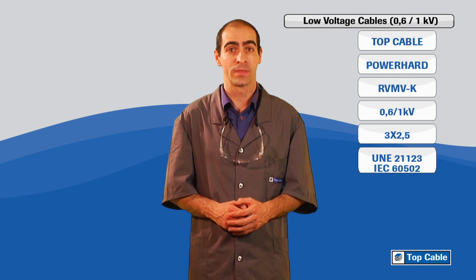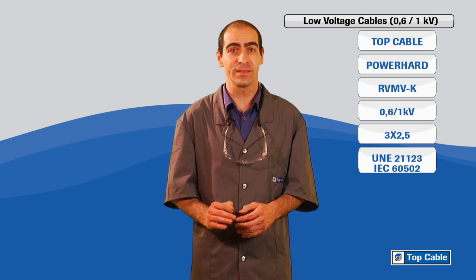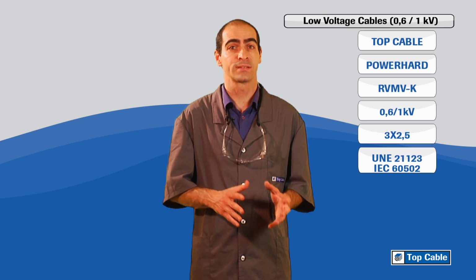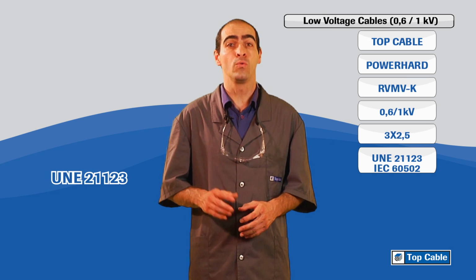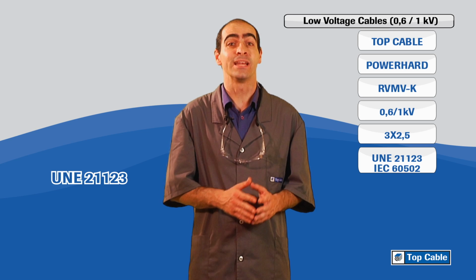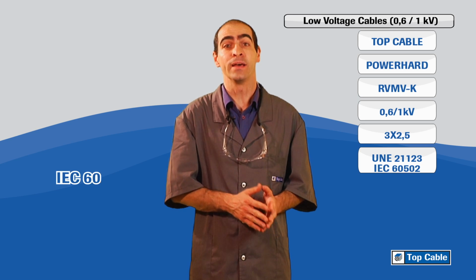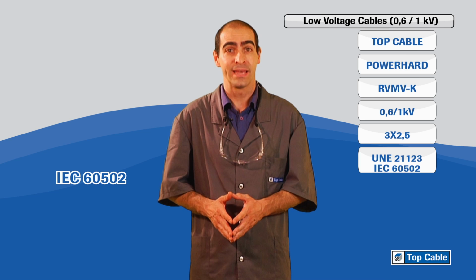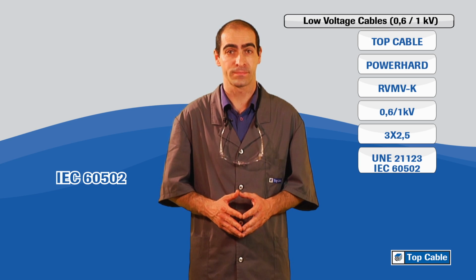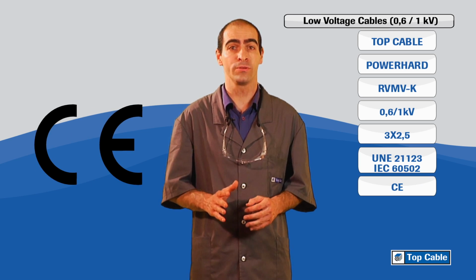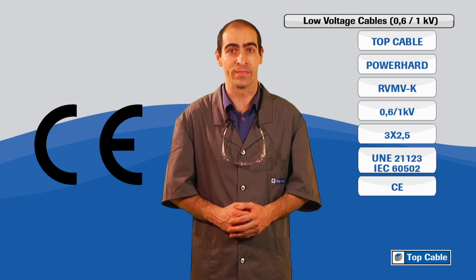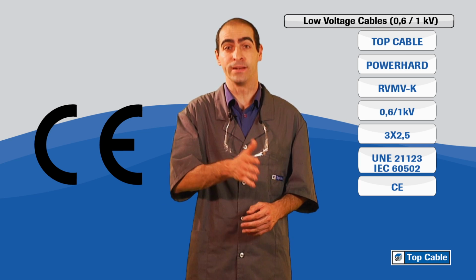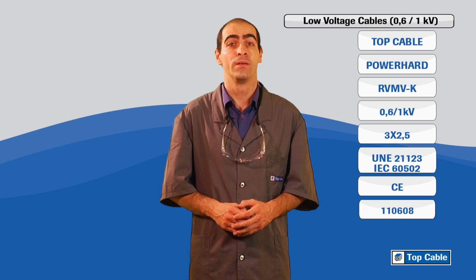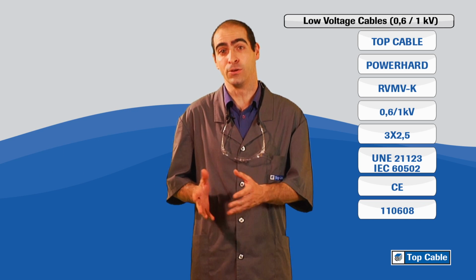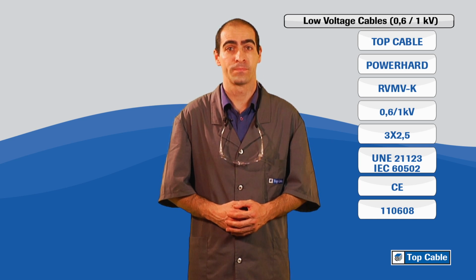Standard for cable design. In these standards, the cable is exactly defined. Thickness, material qualities, tests to be made, and many more. The UNE 21123 is the Spanish design standard. The IEC 60502 is the European standard on which the UNE 21123 is based. Obligatory CE marking for commercial products in the European community. This mark can be on the product or in the packing. Date of manufacturing, years, months, days. In the example, June the 8th, 2011.